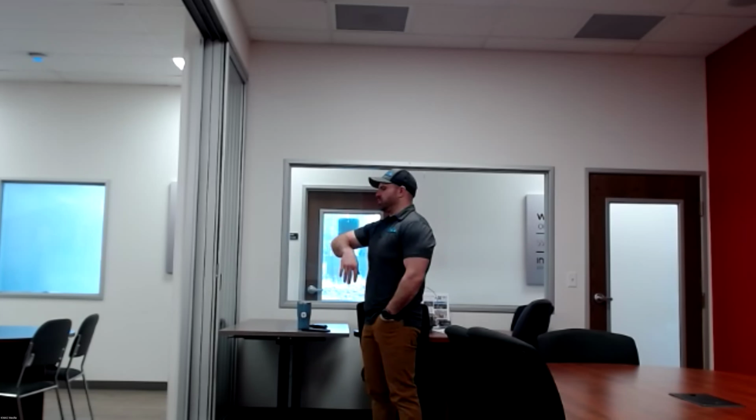So combi units. A combi unit is a boiler and a water heater in one unit. They're usually a wall mounted unit, about twice the size of a standard on-demand water heater, and they're pretty good units also. I have seen issues with really cold well water where the water heater side has a hard time keeping up with a lot of use inside of a home, because it's a pretty small heating jacket that they use. It's about that big.